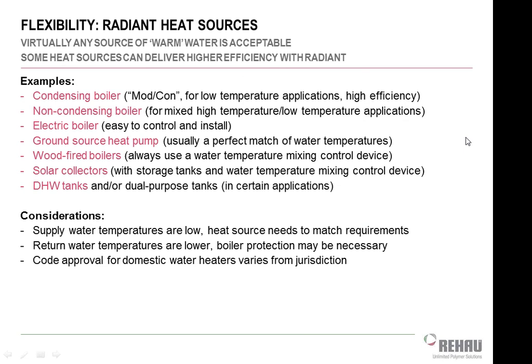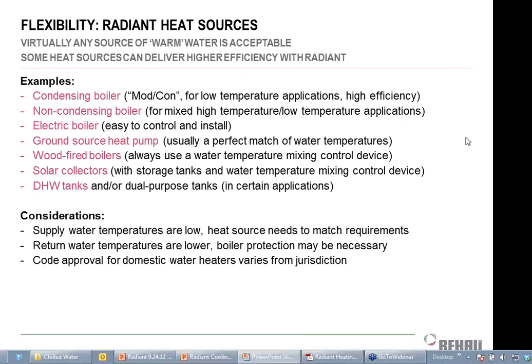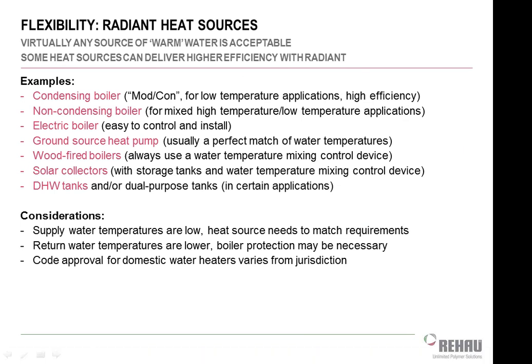So we have to use much lower water temperatures. Radiant systems, we're typically supplying water from the boiler in the range of, let's say, 85 to 110 degrees. The design is going to be somewhere in that range, 110 being kind of the maximum, maybe 115 as an absolute maximum. So you're going to have these lower temperatures. So these radiant systems lend themselves very well to condensing boilers. For you guys that are familiar with boilers, non-condensing boilers, right? It's not that there's some kind of special magic boiler that allows them to condense or non-condense. It's just that the materials that they're made out of can tolerate the condensate.